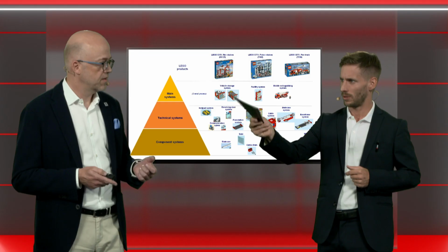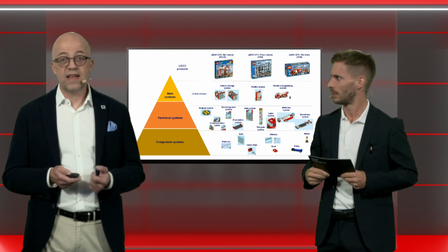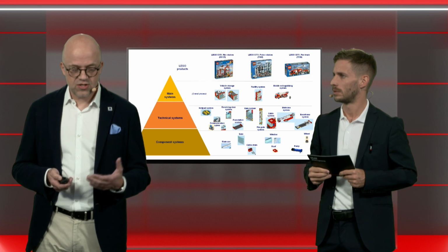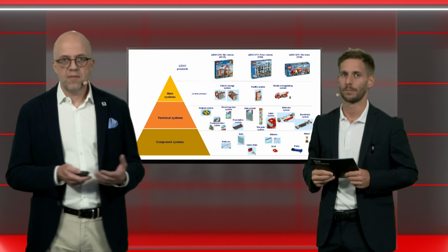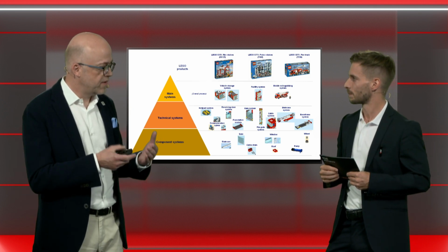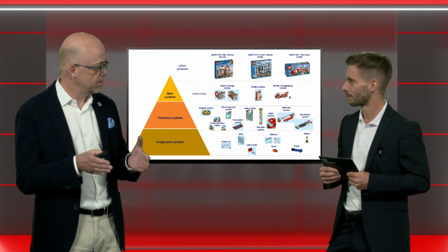Are these 3 levels fixed? That's a very good question, which we often get. First of all, I'll say no, certainly not. It's just a library we pick from. Maybe you recognize also with your customers that very often people have a fixed tag number in their systems. And in fact, that tag number is putting a limitation on how you should think of things. The 81346 standard series is quite clear on that one. It says that you shall have a tree-like structure, which means there's no fixed notation for it.